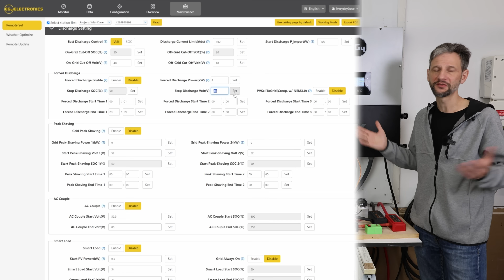I top balanced each one of these batteries individually with 14.4 volts to get them all to 100%. They have CAN communication that's supposed to allow them to talk to each other for balancing during charging, but it might need a Renogy controller to do that. I wasn't able to get it to work by just connecting the batteries to each other, so I'm going to rely on top balancing for now. If I was running this for a long period of time, I would have to come back and top balance them on occasion because eventually they would get out of sync.